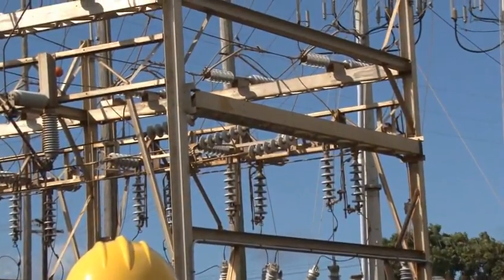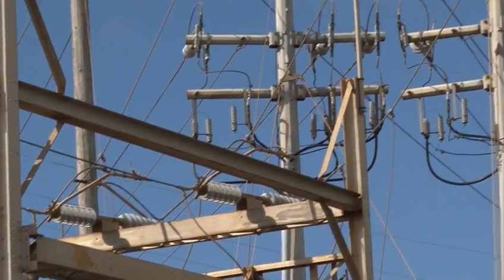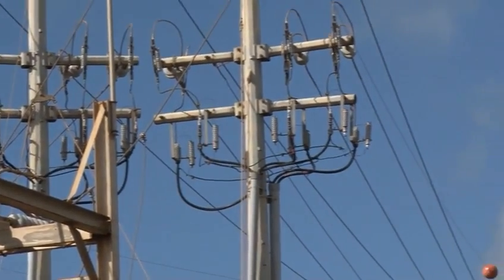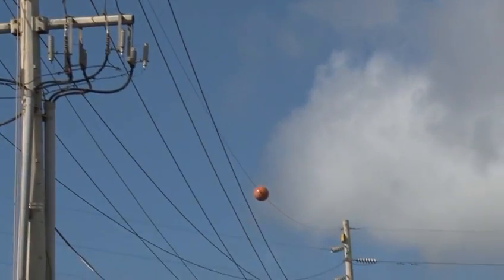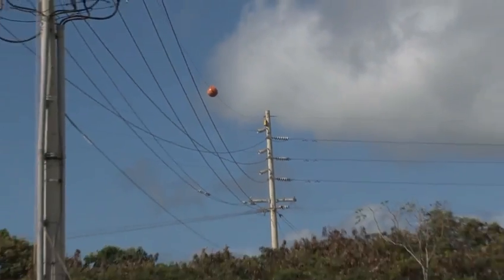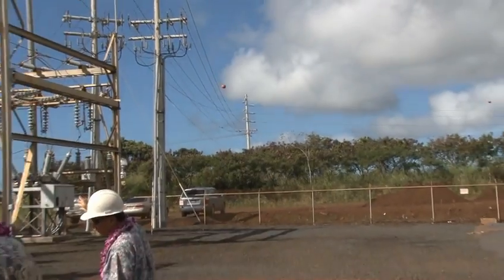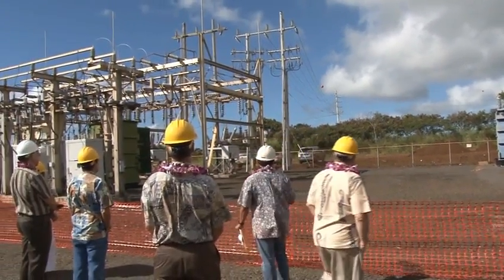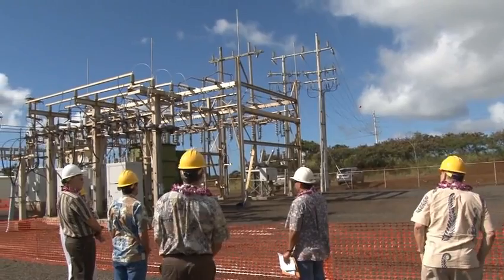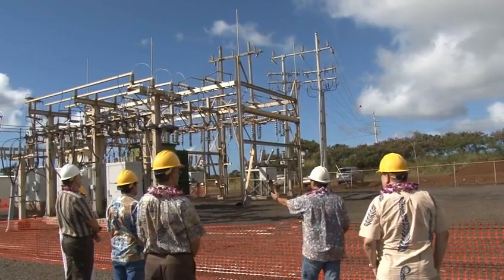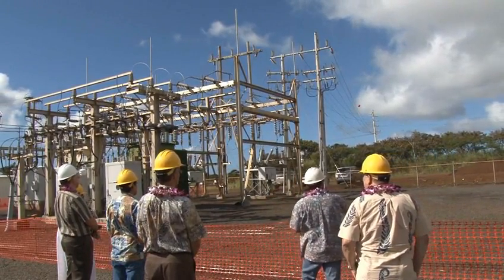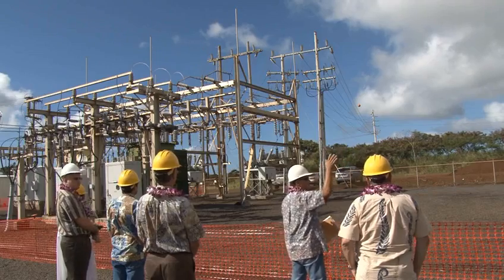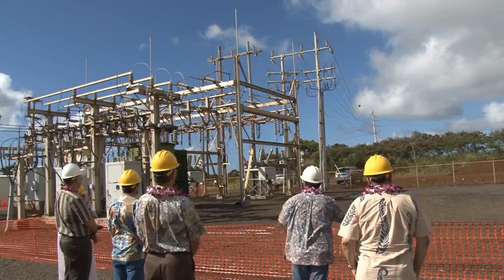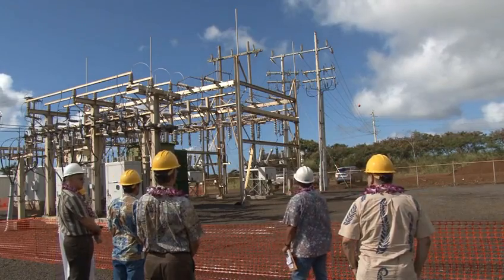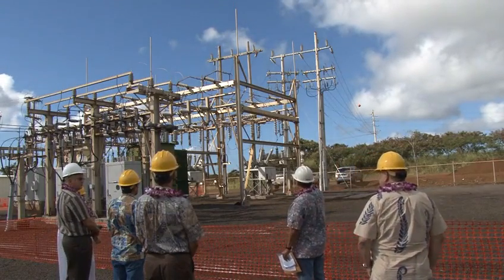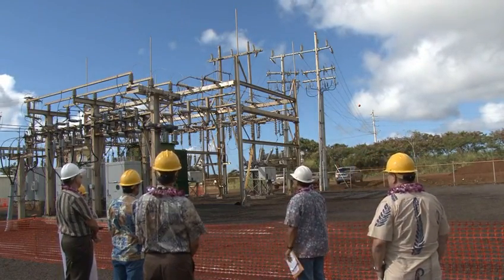So we've got two transmission lines coming in. The one that you see going out and taking off this way actually heads back to Lihue Switchyard. And then the other one drops in, and you can follow it along the road here. That actually is coming from Port Allen Switchyard. So we have a transmission line coming from our Port Allen generating station, coming into Koloa, going out and heading to Lihue, and the Lihue station ties to our Kapaia. So our transmission system is a big loop, and that's the way we get the bulk power over here. And then of course it gets stepped down and distributed throughout.